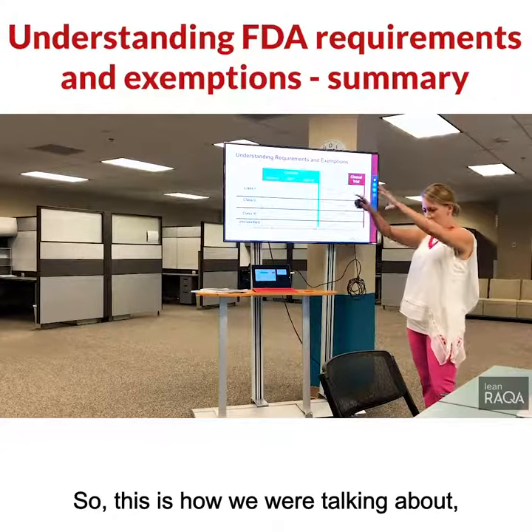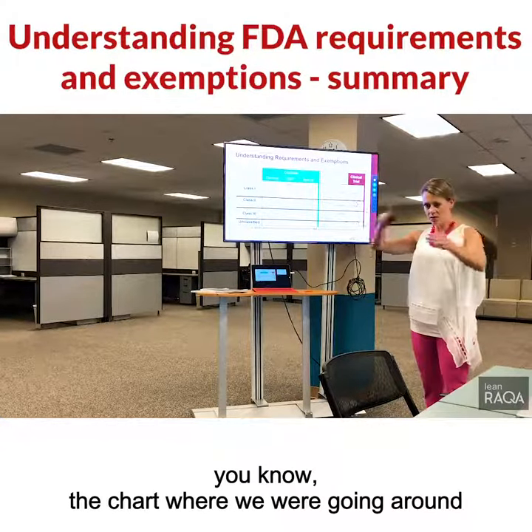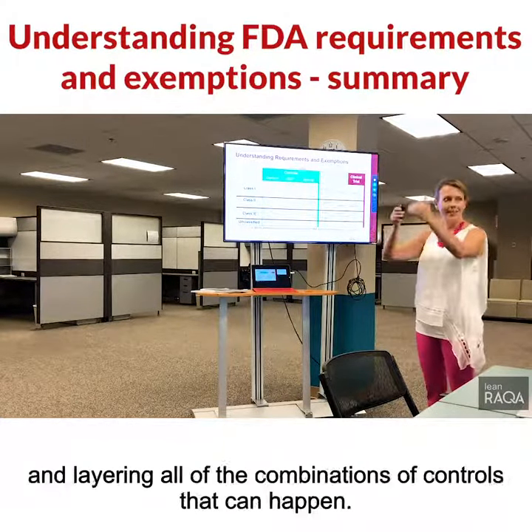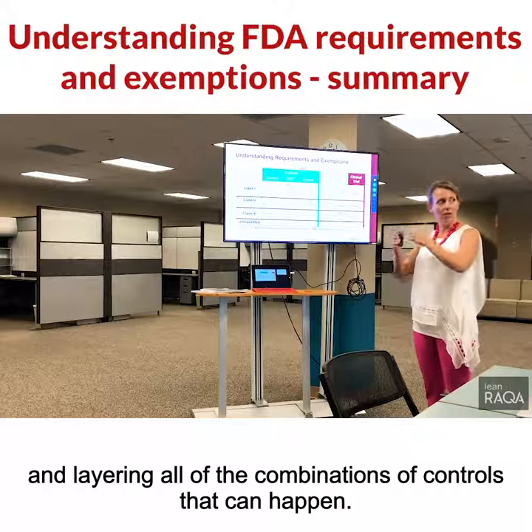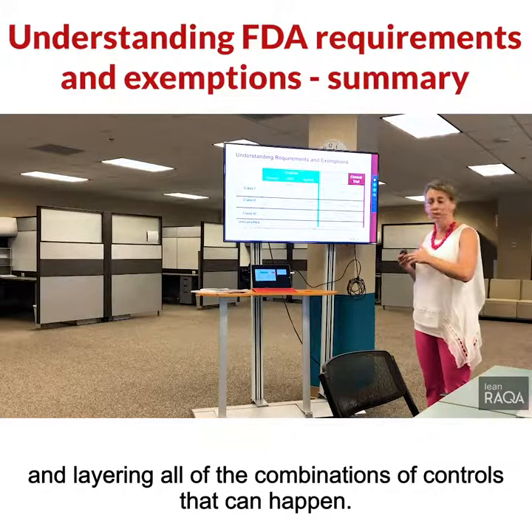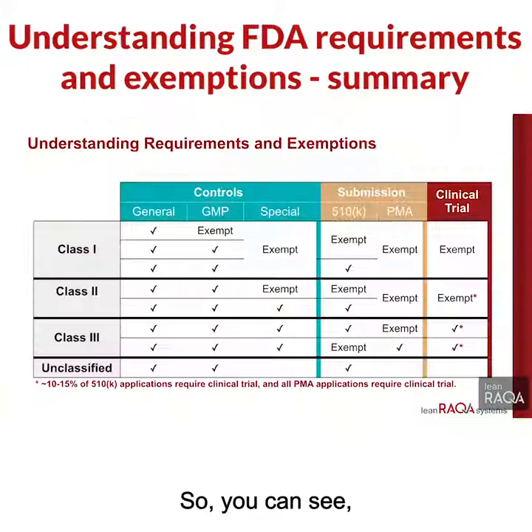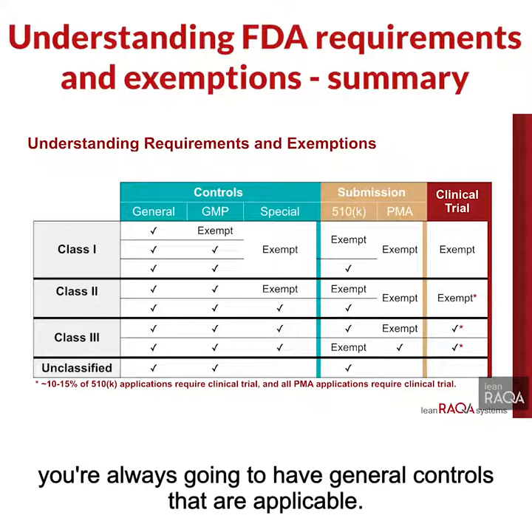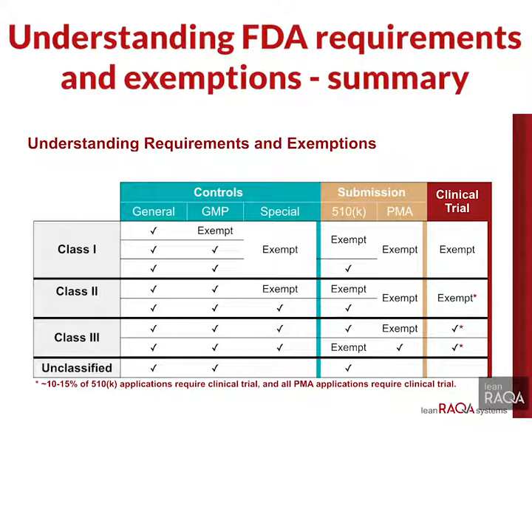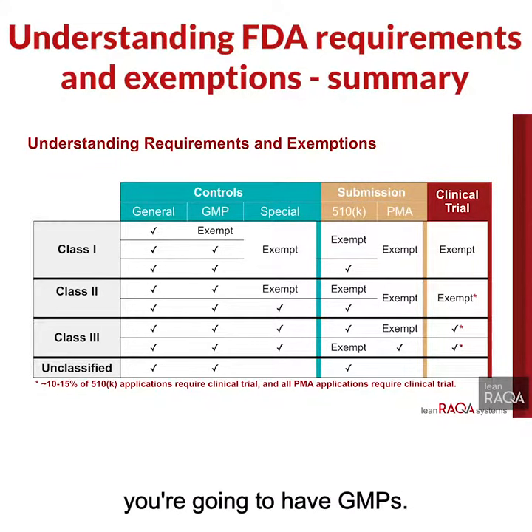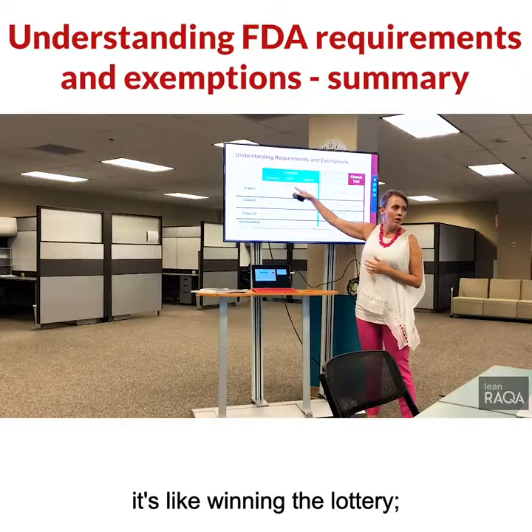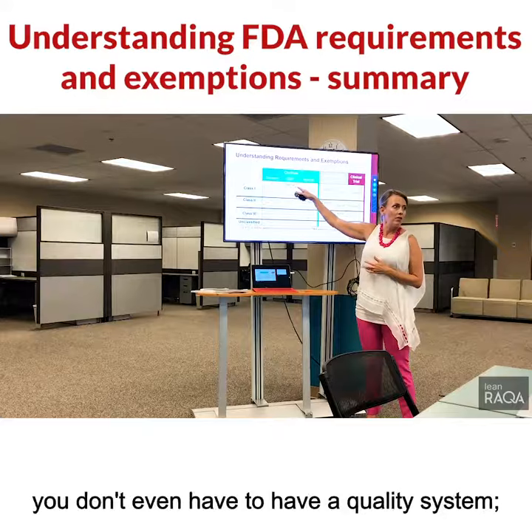So this is how we were talking about the chart where we're going around and layering all of the combinations of controls that can happen. So you can see for class one devices, for all the devices, you're always going to have general controls that are applicable. On top of that, you're going to have GMPs. This is the one where we said it's like winning the lottery — you don't even have to have a quality system.